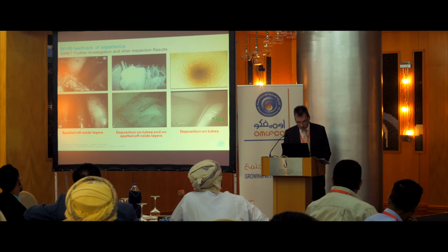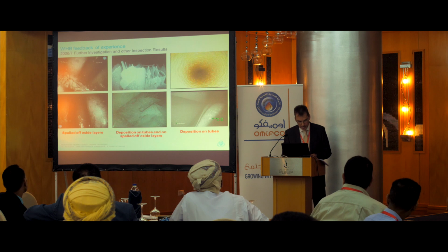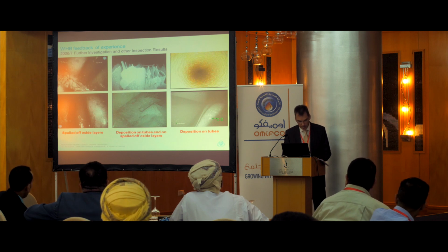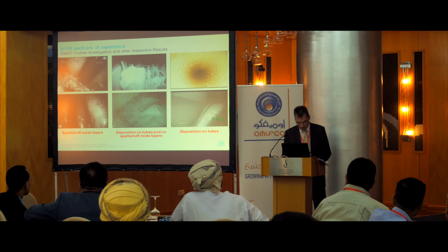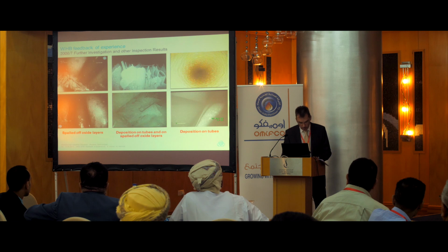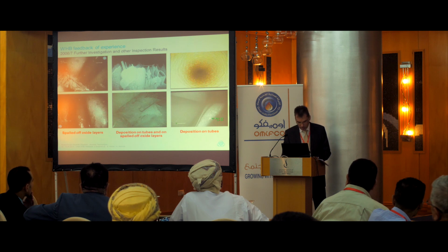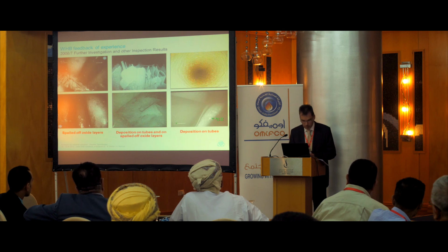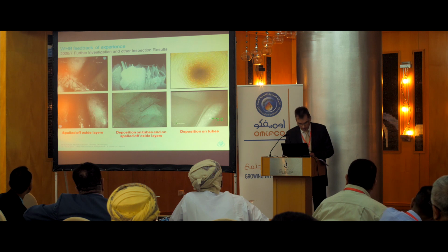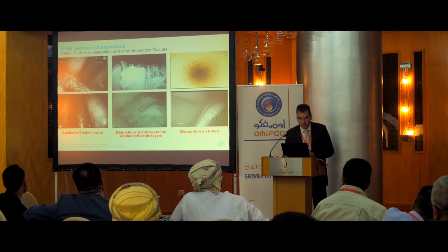From the different inspections, mainly two mechanisms of forming oxide layers were clearly detected. First, oxide layers are formed during post-weld heat treatment and not removed by boil-out during pre-commissioning. They spall off later, during operation of the boiler, and form deposits on tube sheets and baffles. Under these deposits, corrosion can start by concentration of impurities. See left upper photo for deposition. You see it here at the tube sheet. Bottom photo for corrosion damage. Again, when this is washed away and cleaned, you see here these leaking parts of the tubes.